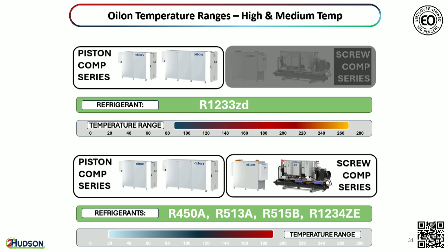Then I want to highlight on the top, the piston compressor units allow for a higher lift. So we use 1233 ZD, which is a very low pressure refrigerant. So you're not going up to like 600 PSIG, you're not going into crazy ranges, and you can get up to 260 degrees Fahrenheit, and we're increasing that at the factory, but I've been told to leave it there. What that does let us do is get up to 15 PSIG steam. So I won't just be covering hot water, domestic hot water, we're covering high temp hydronic, and we're covering low pressure steam applications.